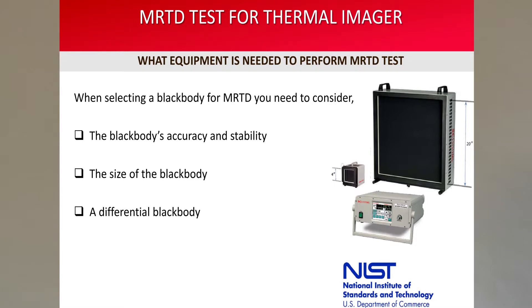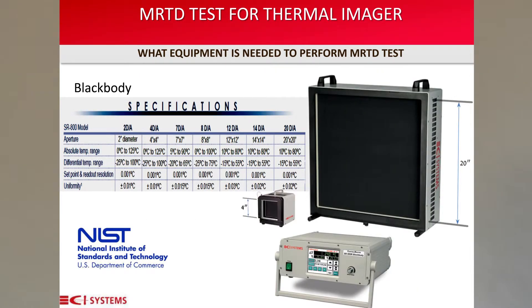When selecting a blackbody for MRTD, you need to consider the following. First, the blackbody's accuracy and stability. Since MRTD testing is often performed in millikelvin resolution, it is important to use an accurate blackbody and also verify that it is certified as NIST traceable. NIST stands for the National Institute of Standards. Second, the size of a blackbody is important. When selecting a blackbody, try to remember that it can also be used for other tests like uniformity. Select a blackbody with a big enough surface area to perform this test as well.